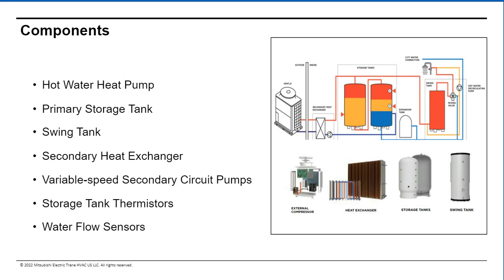There are some changes when you look at the marketplace today. It isn't going to be a drop-in-place replacement for a boiler or a hot water heater today. It takes some things throughout the system to make sure we can achieve those high efficiencies. I'll call out a couple of the major components in the system, and then we'll let others speak on how they interact more. On the left here, you can see we have the CO2 hot water heat pump. In that heat pump is the heat exchanger, compressor, and also a small circulator pump that serves what we call a secondary heat exchanger. The secondary heat exchanger gives you separation from the potable water, but also gives you an easy spot to service and maintain the system, so that if you have poor water quality or fouling over time, you can easily clean that heat exchanger versus having to work on the heat exchanger within the heat pump itself, being CO2 on the other side.